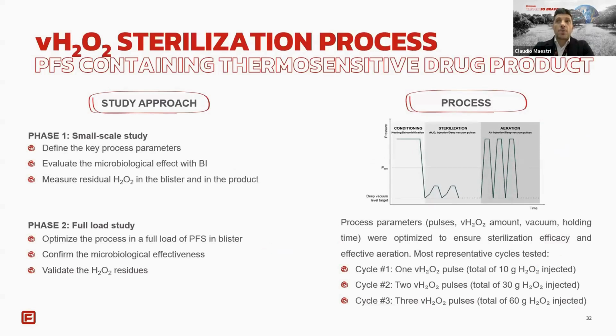The first phase was a small-scale study, defining the key process parameters, evaluating the microbiological effect with biological indicators, and measuring the residual of H2O2 in the blister and in the product. Phase 2 was a full load study, optimizing the process in a full load of PFS in blister, confirming the microbiological effectiveness and validating the H2O2 residues. The process parameters like pulses, H2O2 amount, vacuum, holding time were optimized to ensure sterilization efficacy and effective aeration.